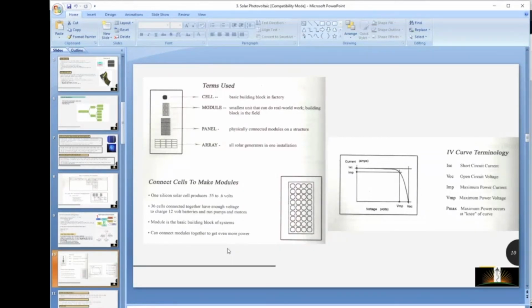Whenever we start the designing part tomorrow, we are going to understand how to design a protection system, because protection system design won't be there in PVSyst, right? In PVSyst, we can take module, inverter, batteries and all. But you need to design a protection system to ensure the whole system is protected. So for the designing part, we need to understand what maximum current we need to design for its safety. That value we are going to get from ISC. So the maximum current that can flow through the system is ISC.